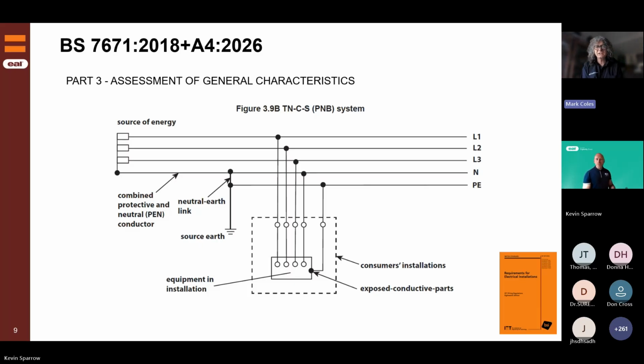There are two variants of the TN-C-S arrangement. TN: terra, meaning earth, as in pomme de terre, apple of the earth, potato, terre is earth. So T is earth, N is neutral, and C is combined. Out in the street you'll find a TNC arrangement, with a combined PEN conductor performing the function of neutral current and earthing. When it gets into the building, it's separated: S, that's TNS.